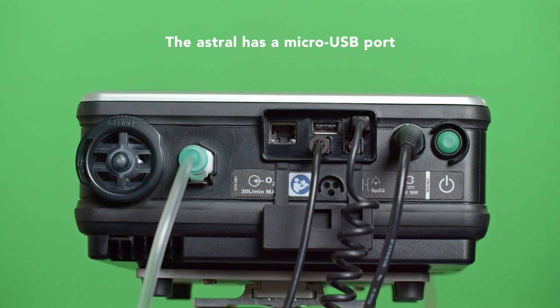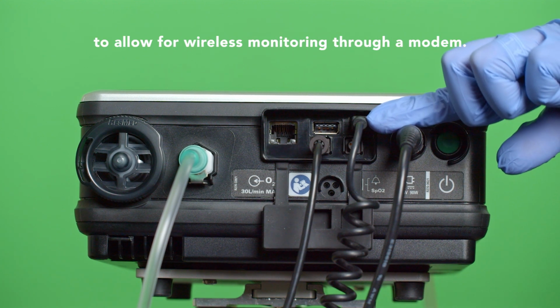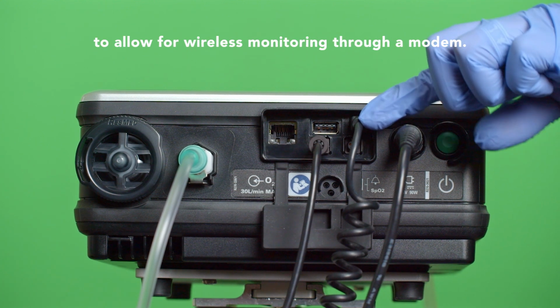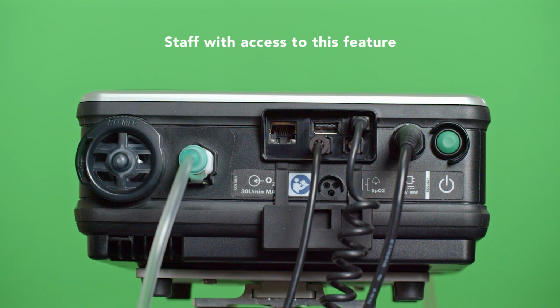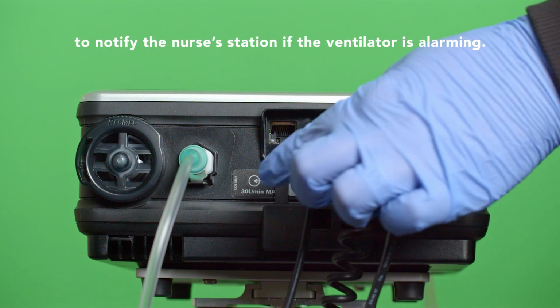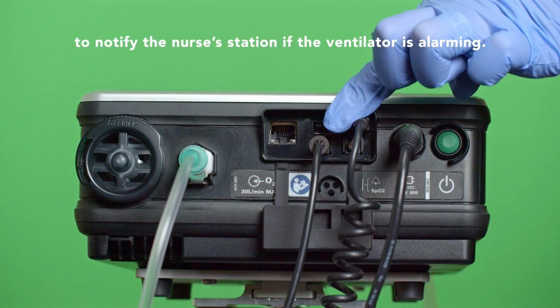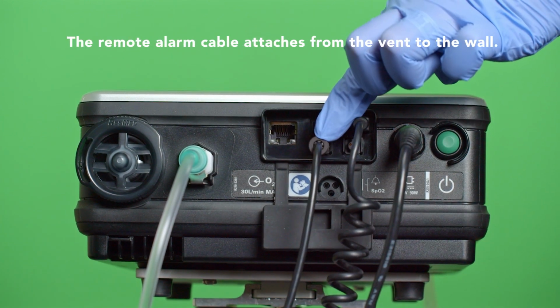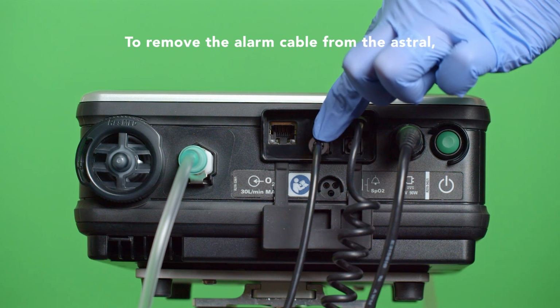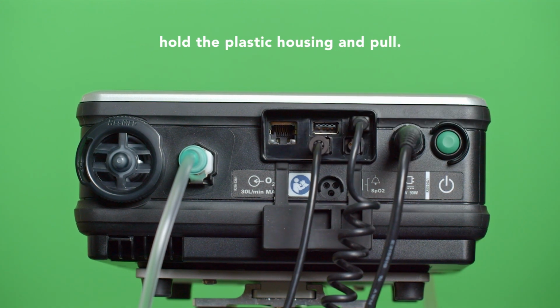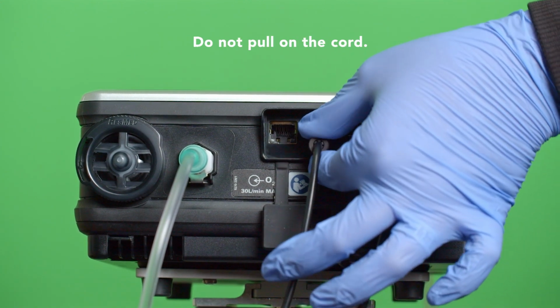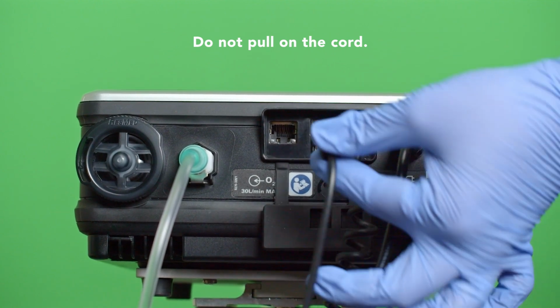The Astral has a micro USB port to allow for wireless monitoring through a modem. Staff with access to this feature can monitor the patient's vent remotely. For patients who have a private room, an alarm cable is needed to notify the nurse's station if the ventilator is alarming. The remote alarm cable attaches from the vent to the wall. To remove the alarm cable from the Astral, hold the plastic housing and pull. Do not pull on the cord.